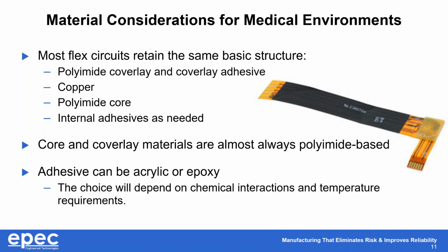However, we can only support acrylic and epoxy, and most manufacturers will probably only support acrylic or epoxy. Your choice between those will go back to anything in your environment that they may interact with. So if you have chemical interactions in a lab setting or temperature requirements for any sort of testing, it's something to consider whenever you're choosing between acrylic or epoxy.